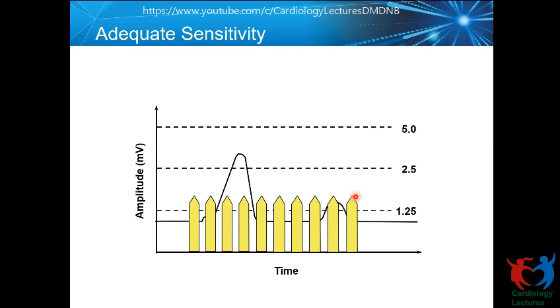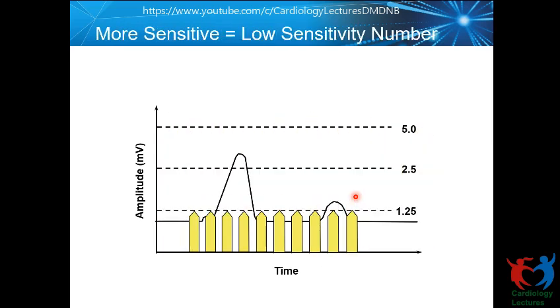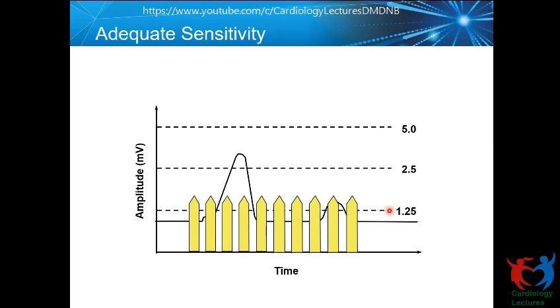But in order to be very safe, if I increase it to, let's say, 2, I'm making the device extremely sensitive. It will sense the R wave. It might sense the T wave also if it does not get filtered in the electromagnetic. So that's a problem that we may come across. Yeah. So optimal sensitivity is around 2.5 we should set, sir. That's best. Yes. And for the R wave, ideally, it should be at least twice your sensitivity setting. It can be more than that, but it should at least be twice your sensitivity setting.